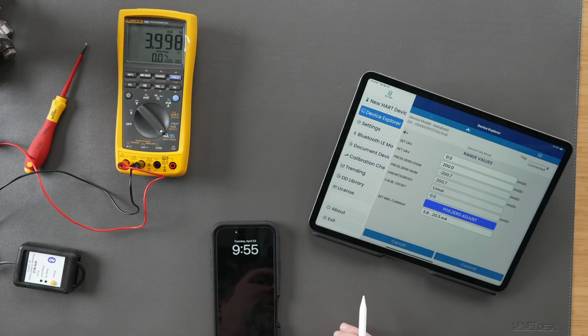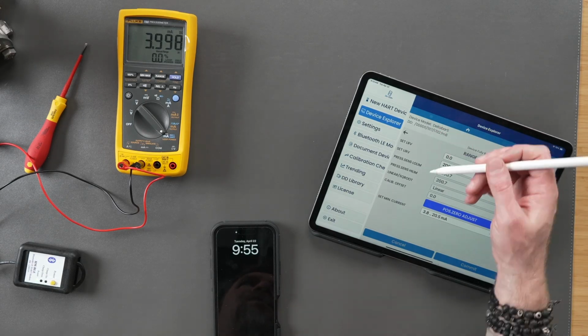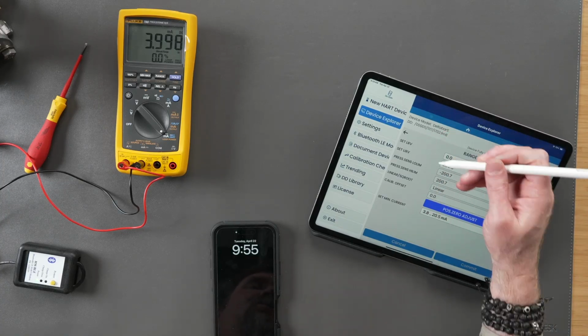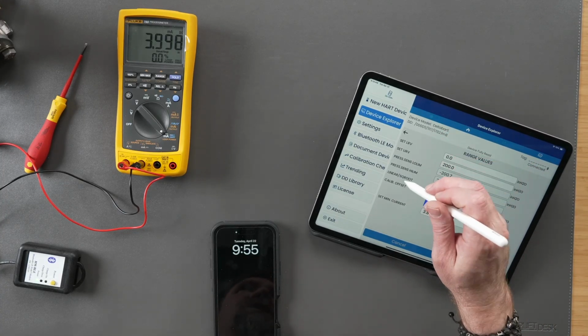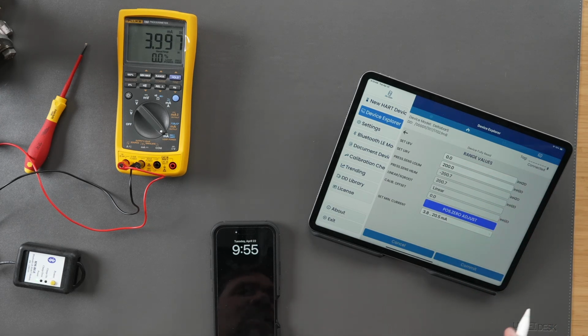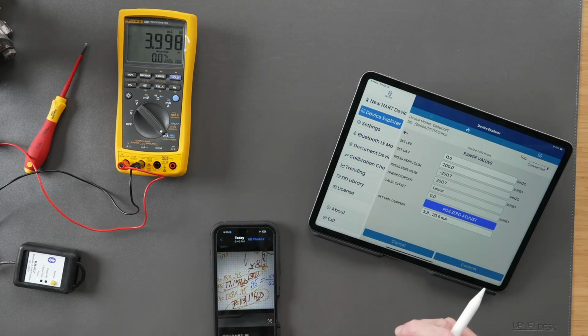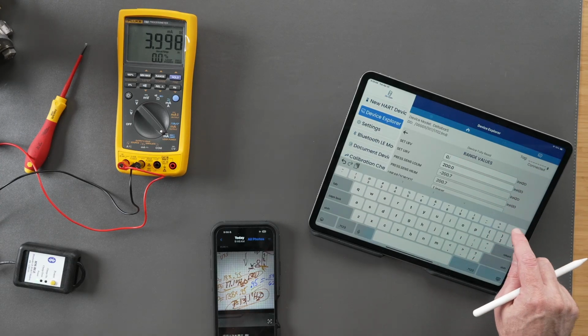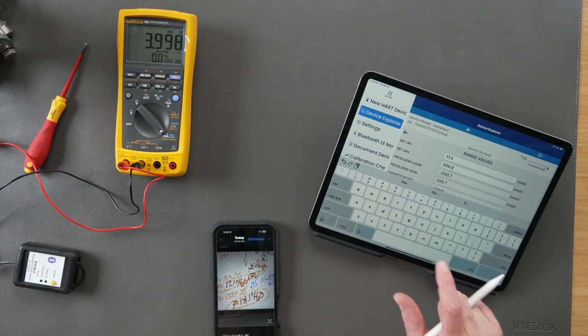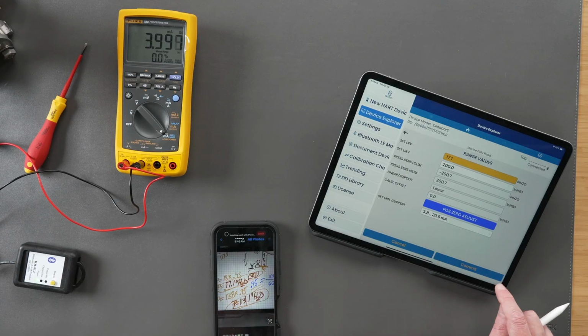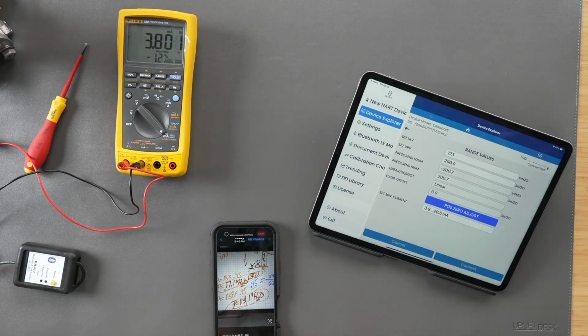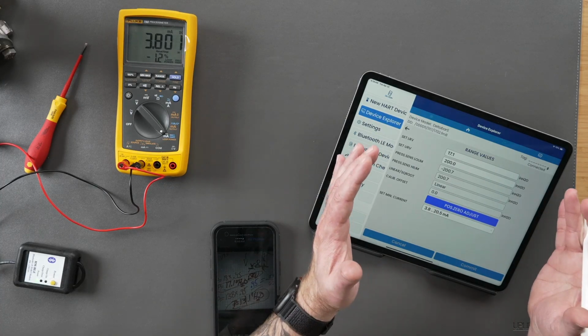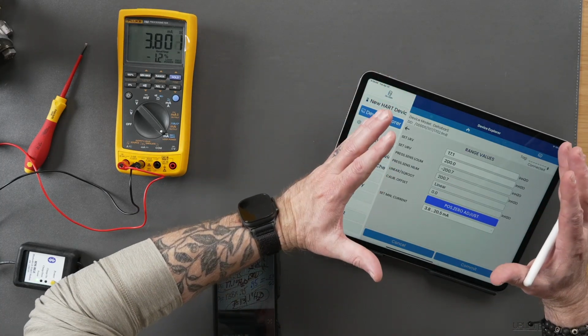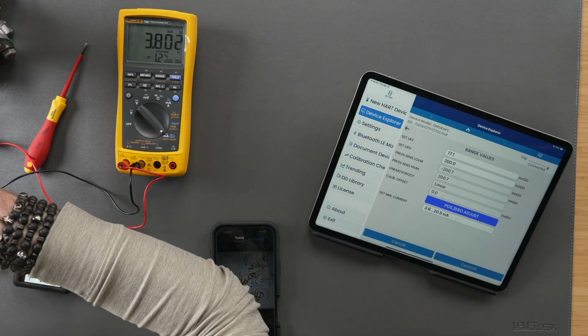Then we're going to go in here and set our LRV and our URV. That might say set 4 milliamps, set 20 milliamps. It might say set 0%, set 100%. So we need to find our picture here. What we needed my pressure at 0%, my LRV value, my 4 milliamps, is going to be 17.1 inches of water column. I'm going to hit that, and then this is like the send. It's a commit. It's taking that information and pushing it to the transmitter, okay? Before I hit commit, it's only at this point. When I hit commit, it pushes that signal this way, okay?